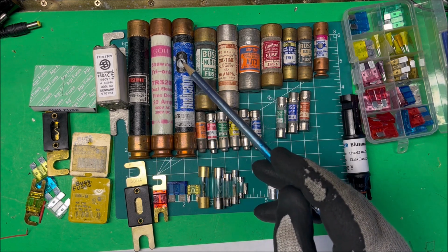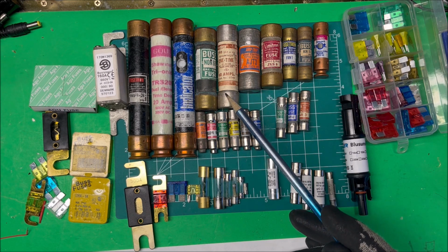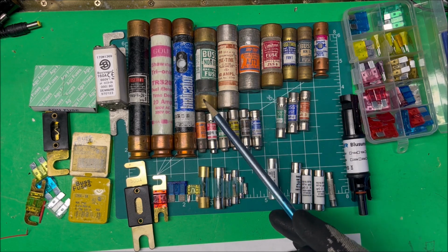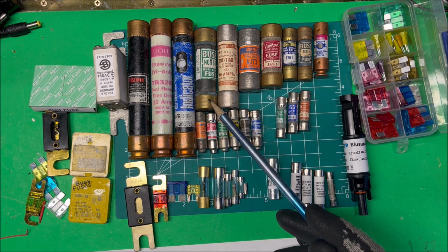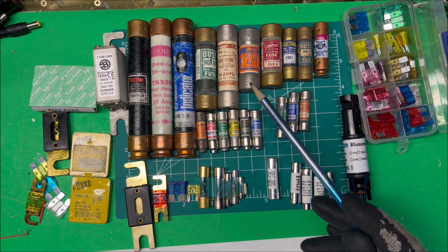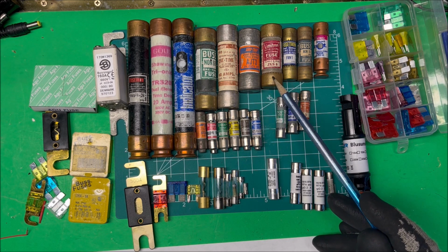This one has a window there so you can see if it's actually tripped or not. These fuses here aren't time delay fuses, but they're for motors, and they're for 250 volts.